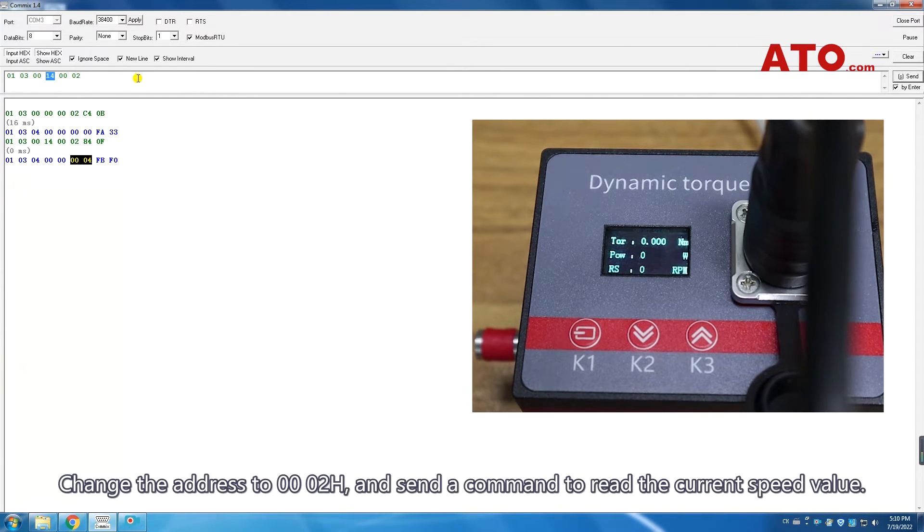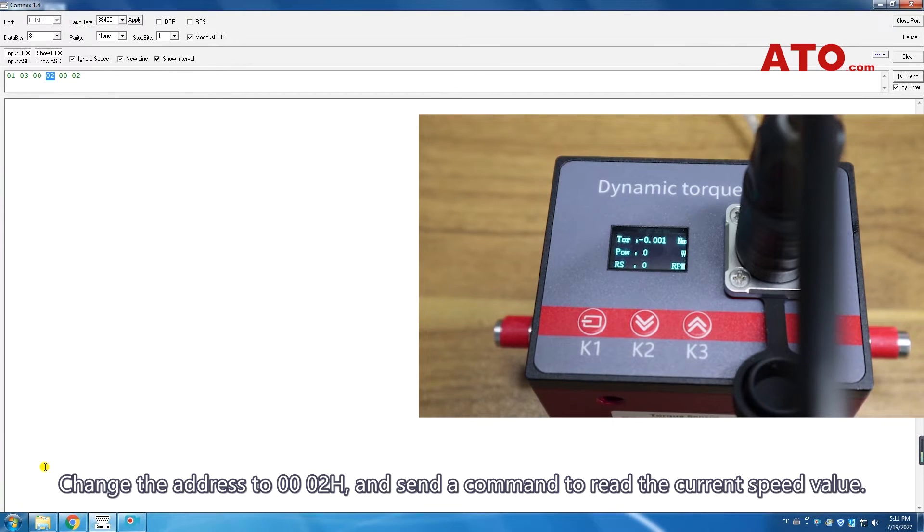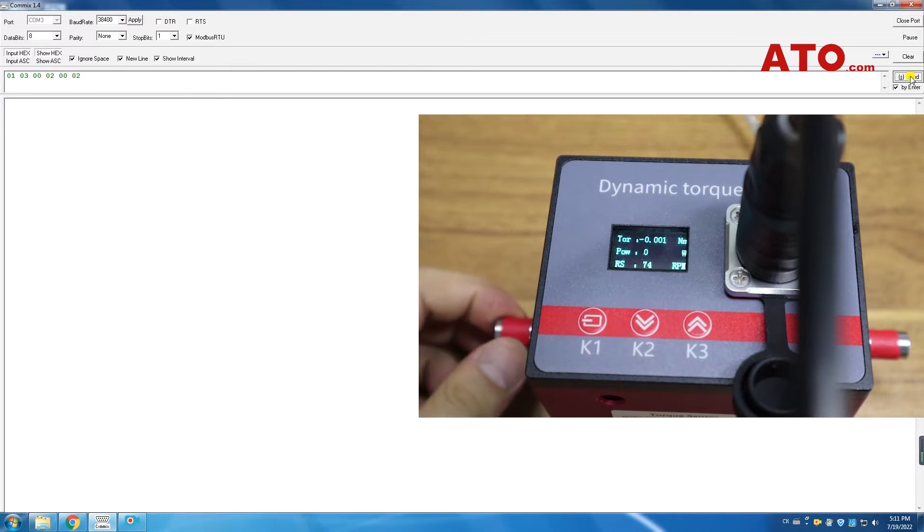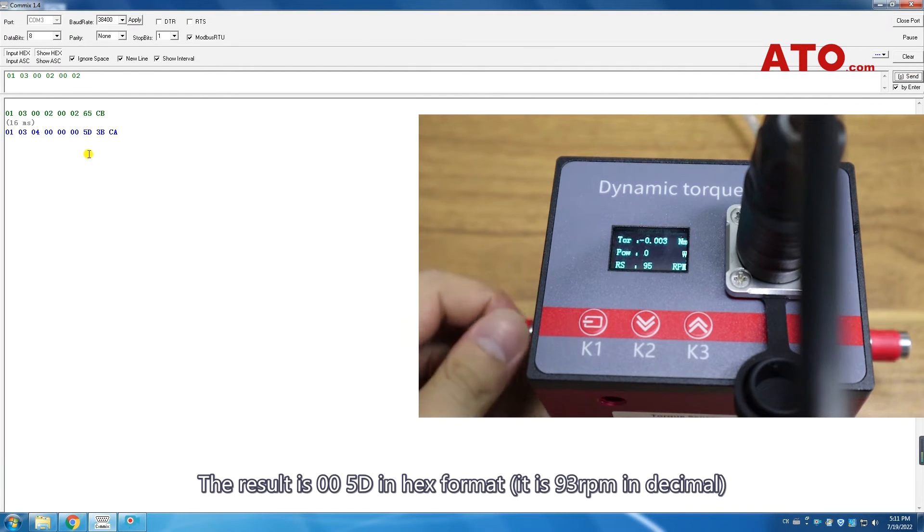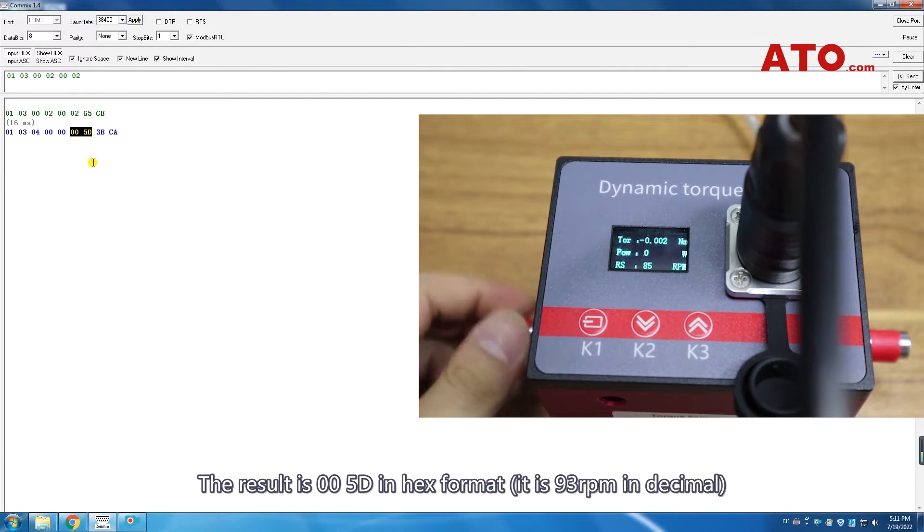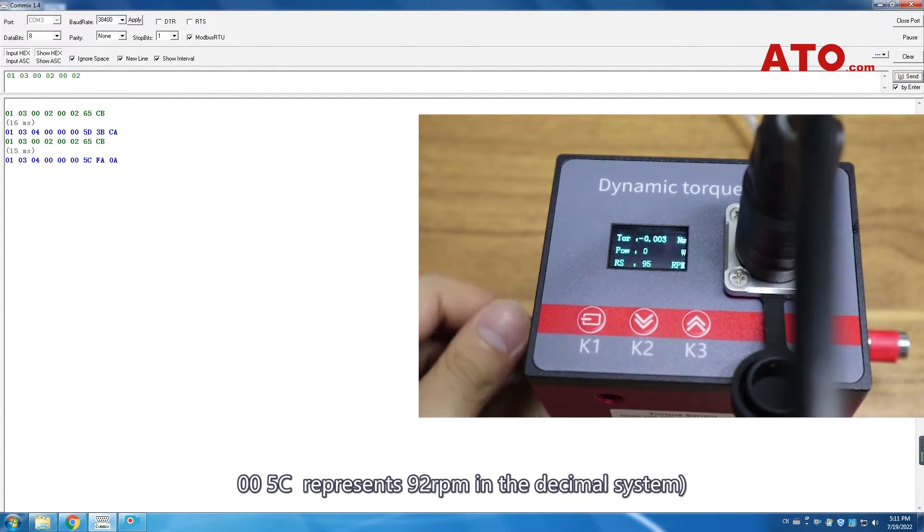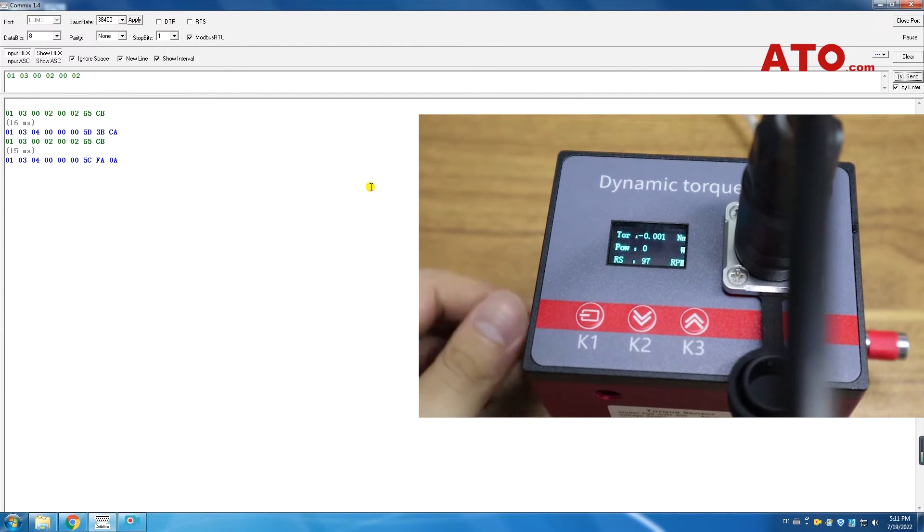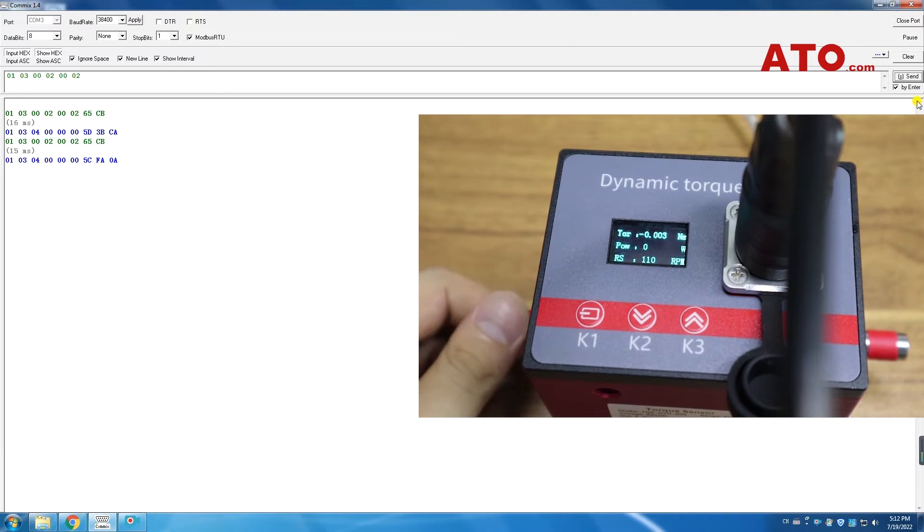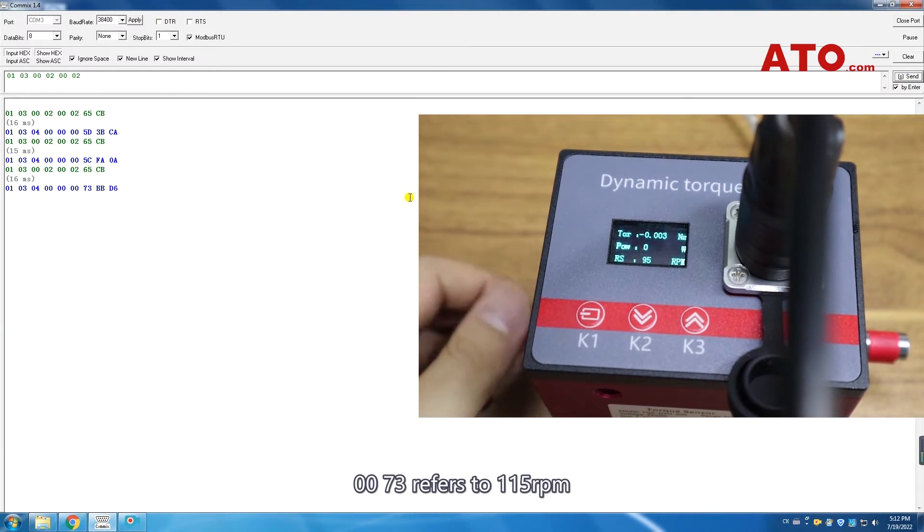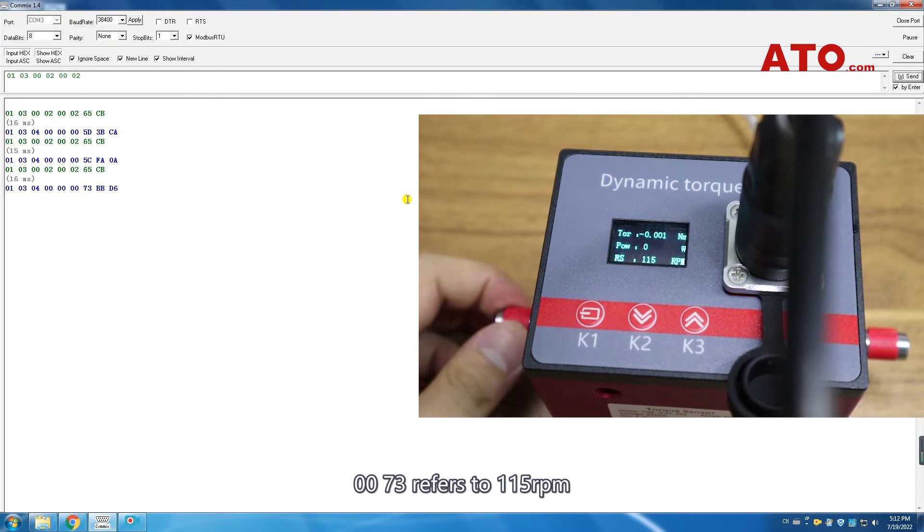Change the address to 000002H and send a command to read the current speed value. The result is 005D in hex format. It is 93 RPM in decimal. 005C represents 92 RPM in decimal system. 0073 refers to 115 RPM.